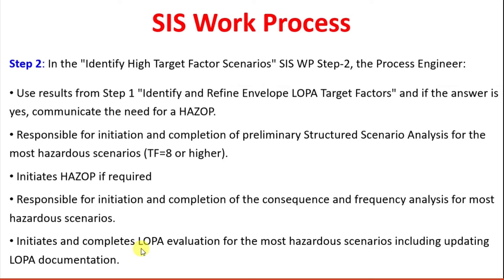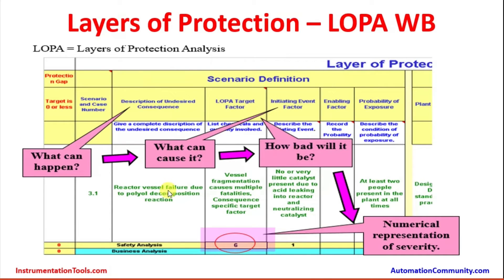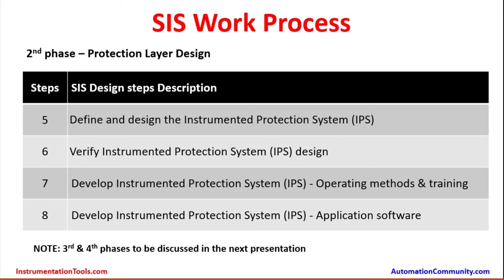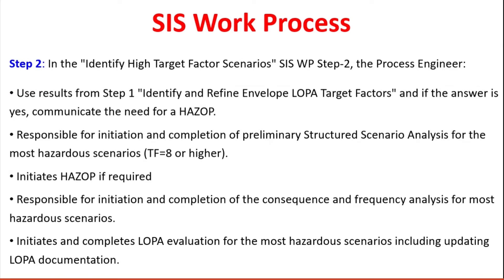They initiate and complete LOPA evaluation for the most hazardous scenarios, including updating LOPA documentation. Multiple scenarios must be analyzed from different angles: hazardous scenarios from a pump failure, motor failure, coupling or bearing failure, switchgear tripping, pump output pressure not developing due to impeller problems, or inadequate suction — all different scenarios that can lead to a hazardous event must be documented in the LOPA documentation.